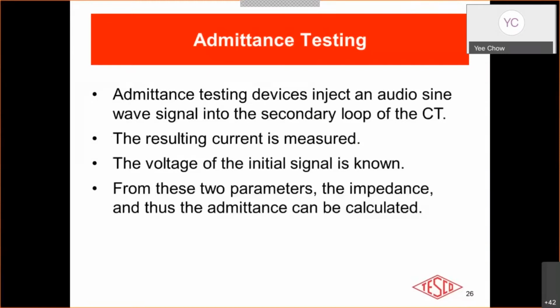Here's how a CT admittance test unit works. It injects a high frequency audio sine wave signal into the secondary loop of the CT, and then measures the resulting current. The voltage that the unit uses is known. Now the current is known, and from those two parameters, the impedance and thus the admittance can be calculated.